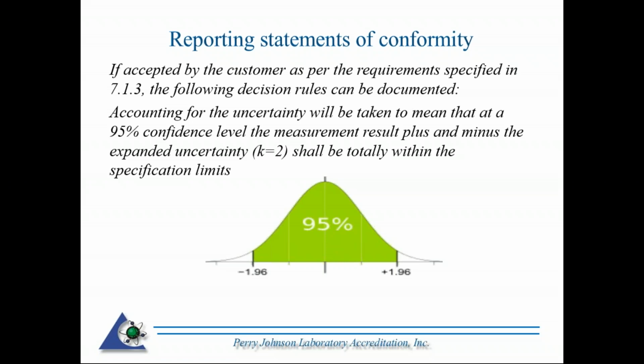So the following is an example of a valid decision rule if you are guard banding and those folks are utilizing a 99% confidence interval. See an example there: accounting for the uncertainty will be taken to mean that at a 95% confidence level, the measurement result plus and minus the expanded uncertainty, k equals 2, shall be totally within the specification limit. So that's basically saying you're not going to state pass or fail unless every measurement is totally within that specification limit. If it happens to fall outside of that specification limit, the uncertainty is actually going to affect that statement of compliance.